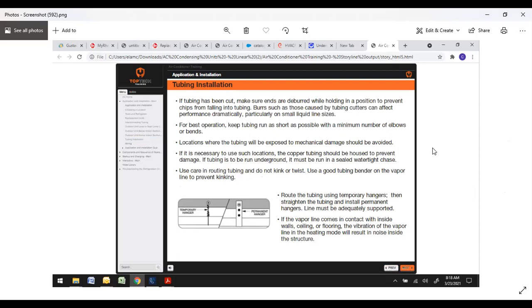Tubing installation. If tubing has been cut, make sure the ends are deburred while holding in a position to prevent chips from falling into the tubing. That's huge. Any one of those little chips get in there, it can plug up a piston, it can plug up a screen, it can foul up your TXV. Burrs such as those caused by tubing cutters can affect performance dramatically. For best operation, keep tubing as short as possible with a minimum number of elbows. Locations where tubing will be exposed to mechanical damage should be avoided. If it is necessary to use such locations, the copper tubing may be housed to prevent damage.